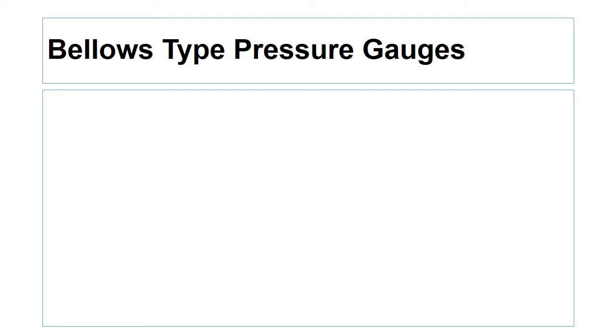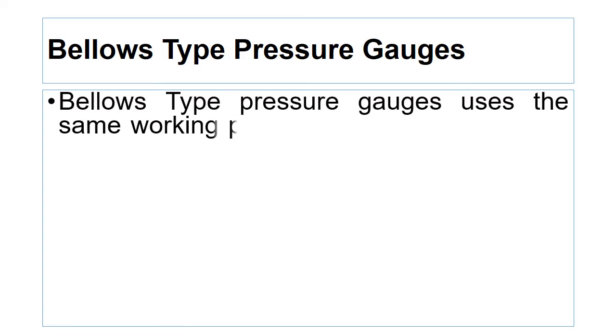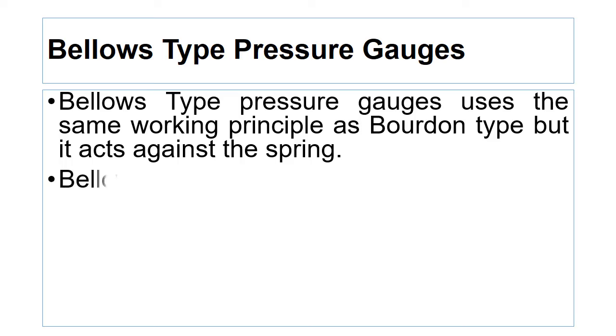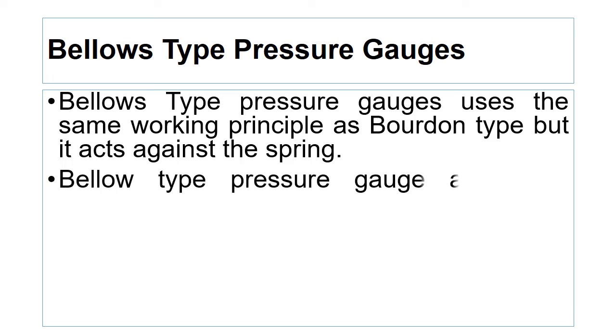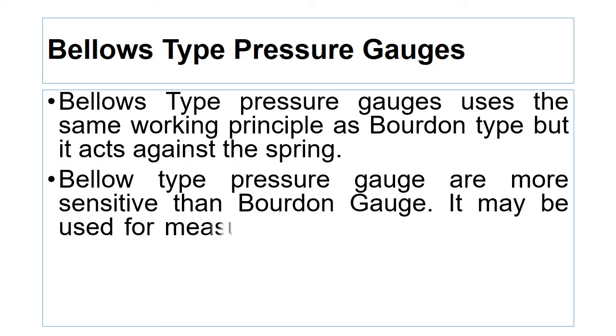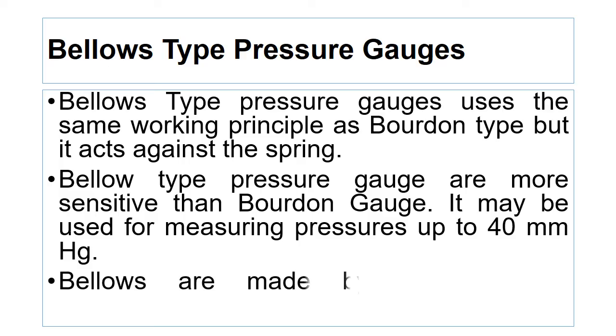The next pressure gauge is the bellows type pressure gauge. Bellows type pressure gauges use the same working principle as the Bourdon type pressure gauge, but act against a spring. Bellows type pressure gauges are more sensitive than Bourdon type pressure gauges and may be used for measuring pressure up to 40 mm mercury column. Bellows are made by joining many diaphragms together.